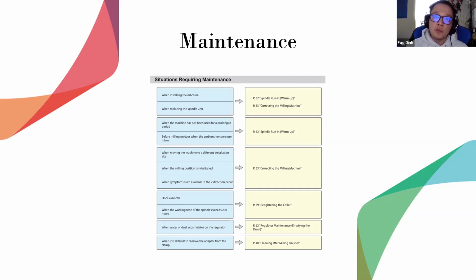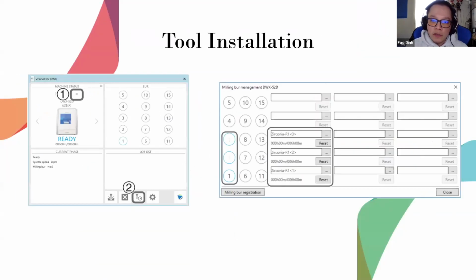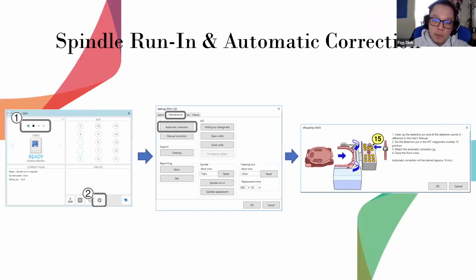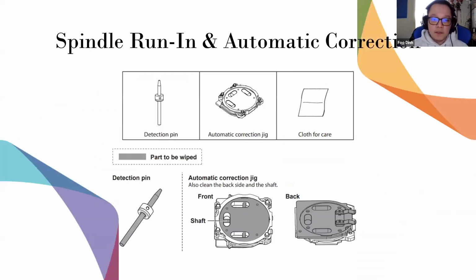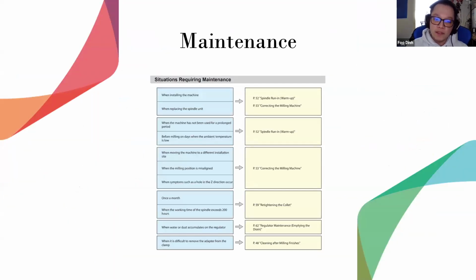Tightening the collet, like we mentioned earlier, once a month or every 200 hours of mill use. Okay, actual milling time. Within the V panel, it tells you right here, the spindle time, work time in the middle of the screen. Right now it says 7 hours, 8 minutes. When you see that hit around 200 hours, we want to do collet maintenance. Okay, after the collet maintenance, do a calibration.